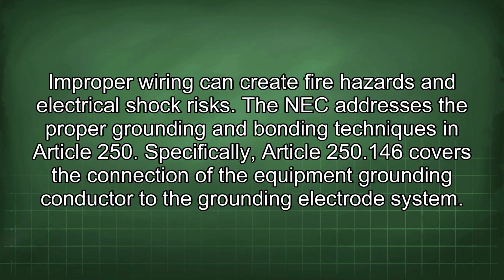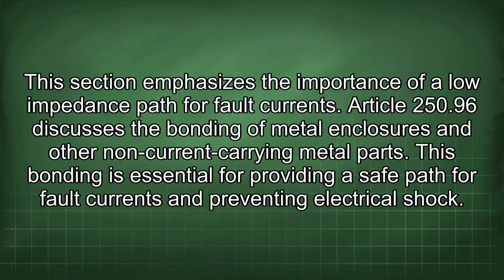Improper wiring can create fire hazards and electrical shock risks. The NEC addresses the proper grounding and bonding techniques in Article 250. Specifically, Article 250.146 covers the connection of the equipment grounding conductor to the grounding electrode system. This section emphasizes the importance of a low impedance path for fault currents.